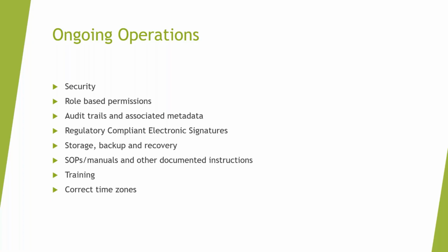And then we've got security. So role-based and physical security logical controls are in place to restrict access to the computerized system and/or data integrity to authorized persons. The role-based permissions is one of the most important areas, including those to enter, change, deletion, approval and archiving. It's really important that they've got a good oversight over those role-based permissions, so not just the allocation, but also ensuring that there's not multiple roles assigned to the same person.